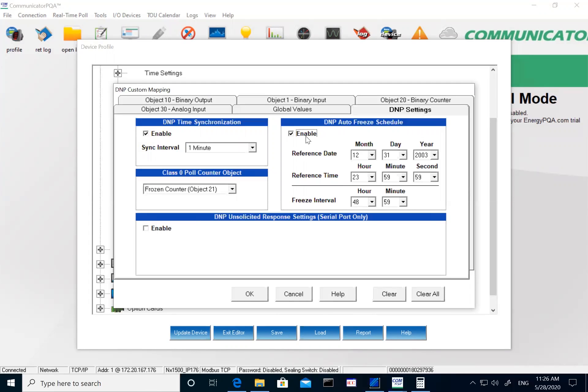The auto freeze schedule lets you freeze the meter's registers on a periodic basis. Some customers use it to freeze registers on a daily or monthly basis. When the freeze schedule occurs, the meter takes a snapshot of your current readings — energy, maximum demand, voltage, current — and puts them into a different set of registers you can pull afterward. For example, freezing monthly lets you download that information to calculate your bill, giving you monthly kWh consumption and maximum demand.